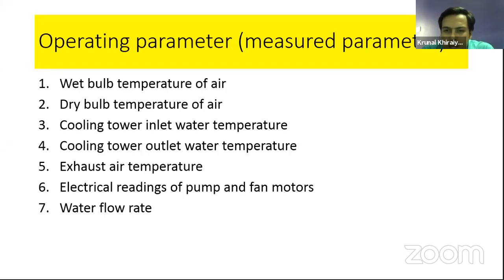Venturi meter, Viral Gandhi is saying, yes, Venturi meter. No, you cannot use this kind of device because it is a closed type, from the pump curve with the pressures. Jigar Patel says from pump curve. Okay, no. Rotameter, I repeatedly get the answer. Some say a pitot tube. No. Anyone? Yes, N.T. Rana says ultrasound. Yes, very good. Whenever you don't have access to measure the fluid in contact with the fluid, then we use ultrasonic flow meters. Yes, an ultrasonic flow meter is used for water flow rate measurement.